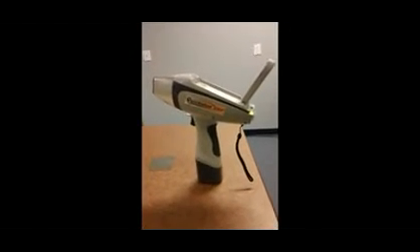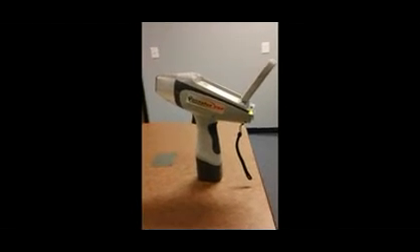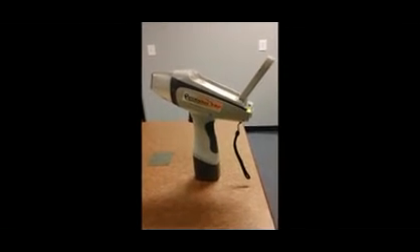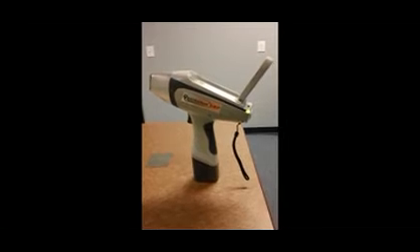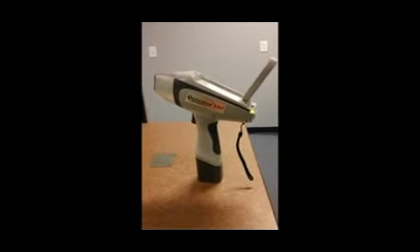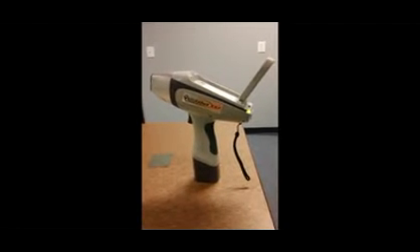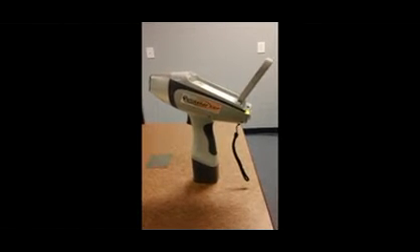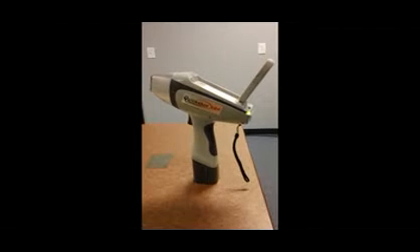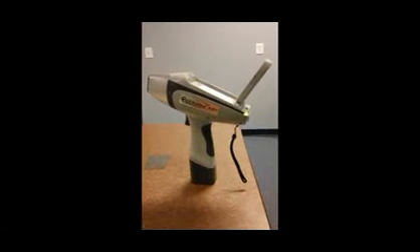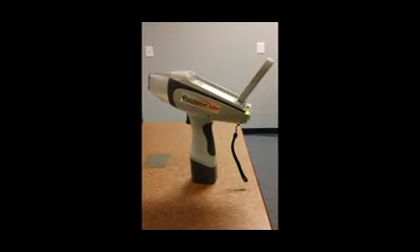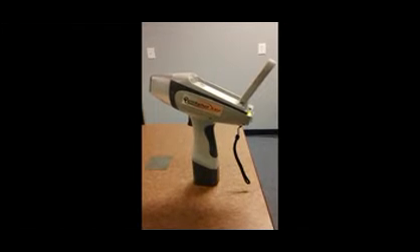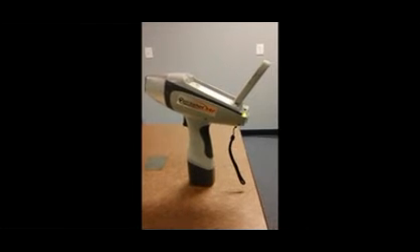Today, we're looking at a demo version of the newest QuickShot XRF handheld analyzer. This system expands on the capabilities of the previous handheld model and features a silicon drift detector technology, which allows for faster measurement times, greater resolution, and overall expanded application performance.